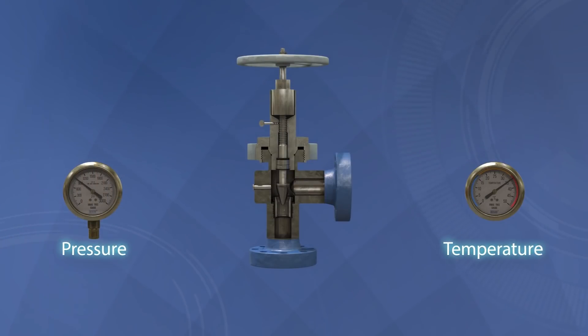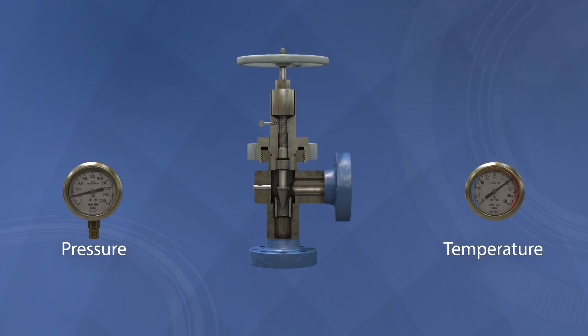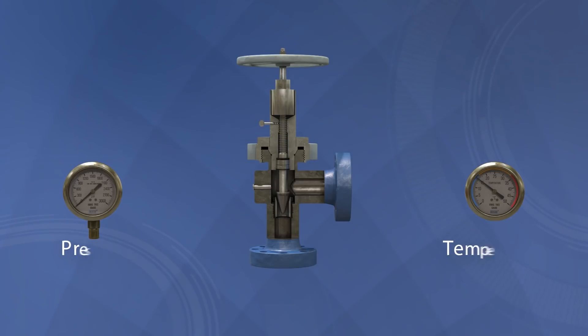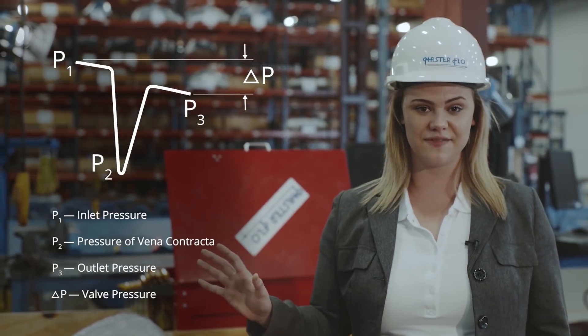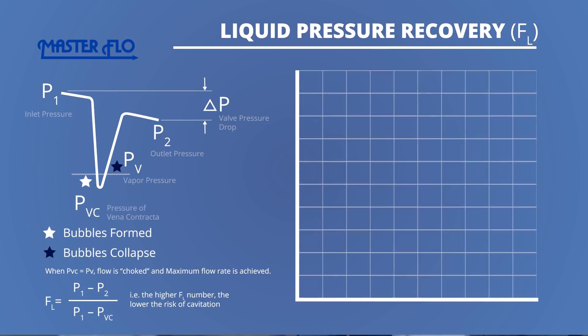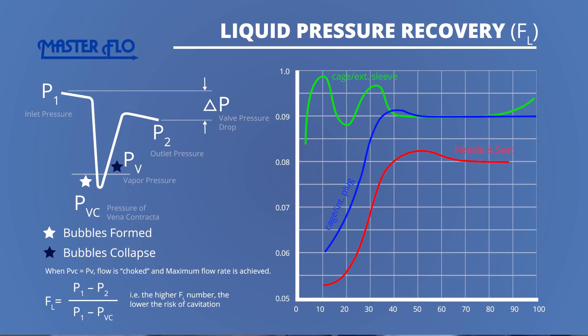If the pressure in the choke falls below the vapor pressure of the liquid, cavitation may occur. When this happens, the pressure is greatly reduced in the valve. The susceptibility to cavitation is governed by the valve FL number, which determines how low the pressure can get inside the valve. In extreme cases, freezing of gas may occur in the choke valve due to hydrate formation. The cage with the external sleeve design provides a higher FL over a wider range of valve openings, meaning a lower chance of cavitation and consequently less risk of damage.